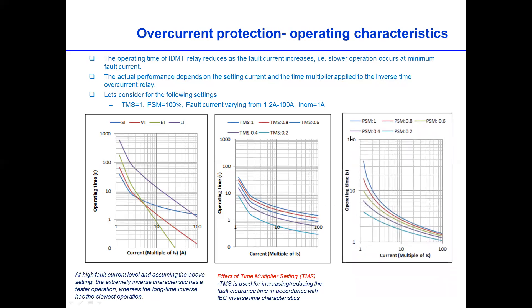Another example is we can also vary the PSM from, for example, 100% with addition to various cases. So let's have a look. If you look at this one at 100% trip time was similar to what we were discussing. But then when we reduce to 0.2 or 20% then it is lower. Meaning that we can play with the setting current. We can lower the setting current based on the specified value. So PSM is mainly used to adapt the relay pickup setting current. The setting can be varied by considering maximum loading current of the relay.